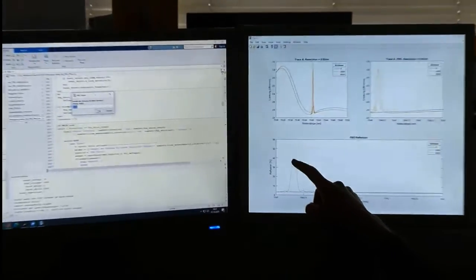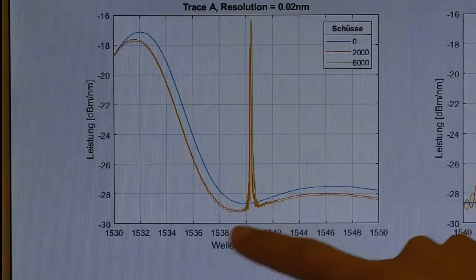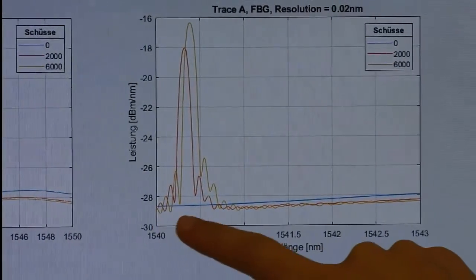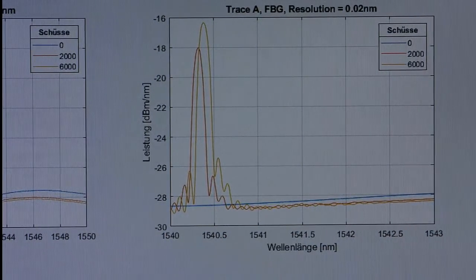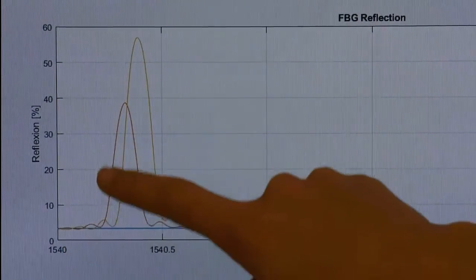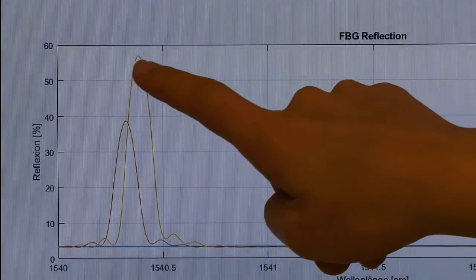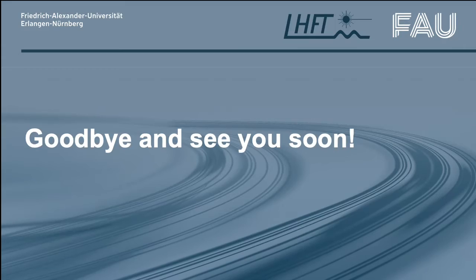In the last step we also look at the inscribed grating and the measurement data at the computer. Here you can see the measurement curves from before the inscription and of the two inscription steps we have performed. We see that after the first inscription our grating was close to 40% reflectivity and after the second process it has 58% reflectivity. The FBG looks great. Good work. See you next time in our laser lab.